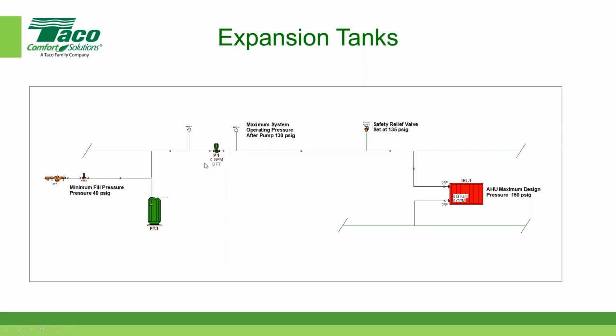Well, if the pump has the capability of adding 20 pounds to the system, then that means the pressure I want at the suction side of the pump, which in our example is the maximum pressure that I want at the expansion tank, if the pump can add 20, then 130 minus 20 is 110. There's the 20 pounds across the pump. So I want a maximum system operating pressure at the pump suction, which is also at the expansion tank, to be 110 PSIG. Any questions about how I figured out the maximum pressure?